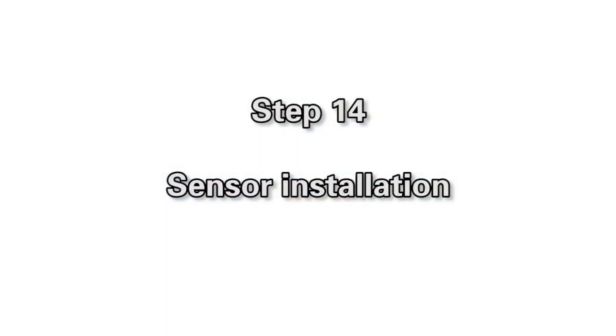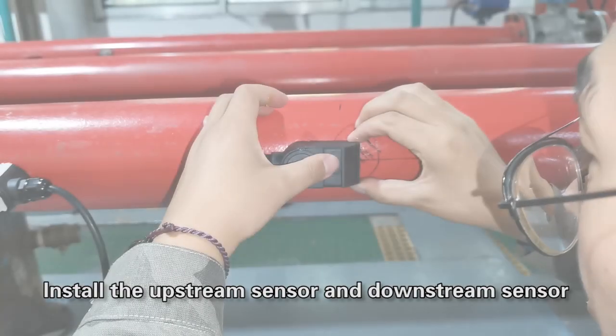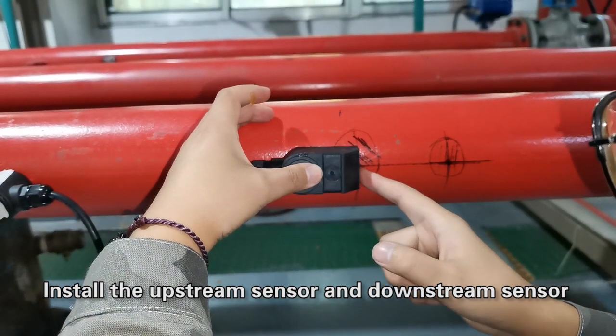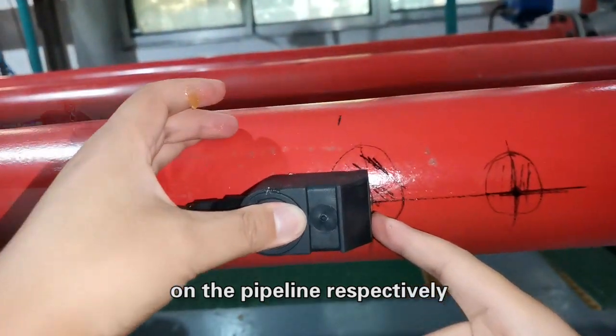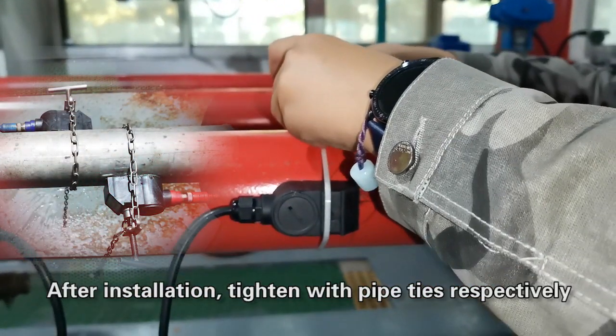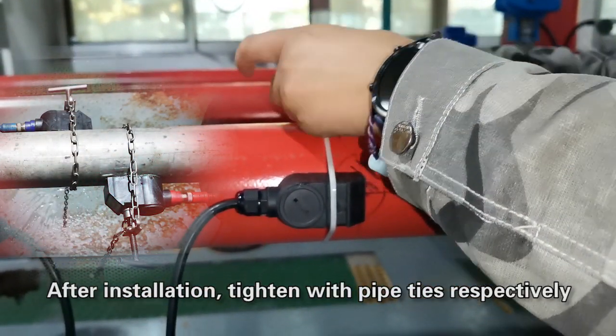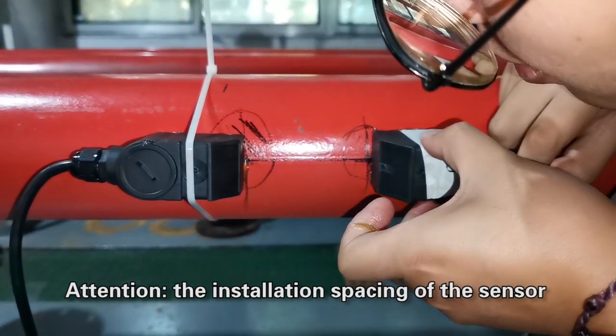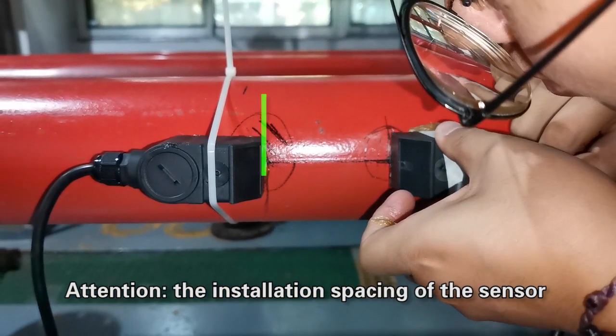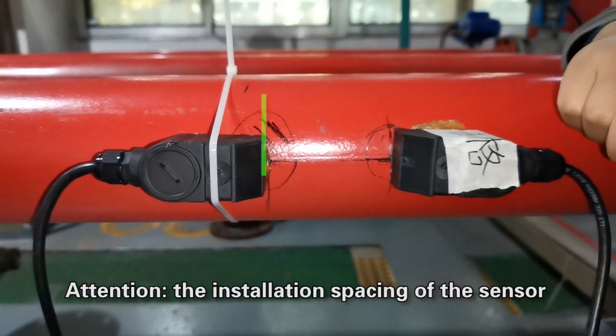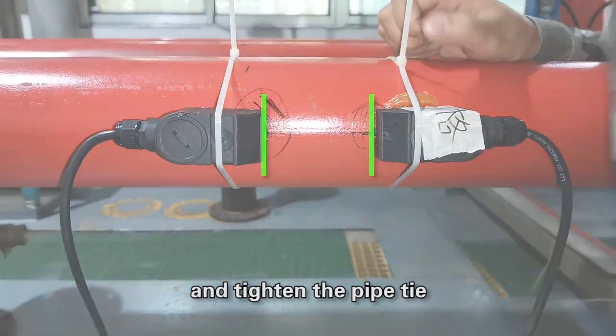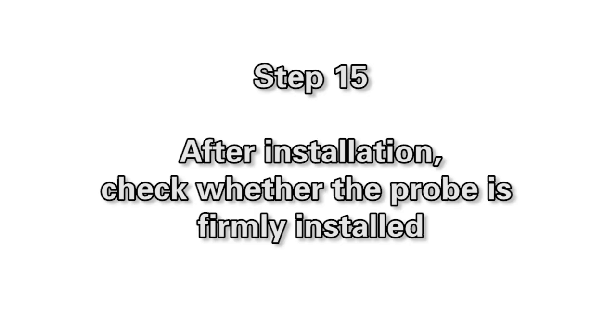Step 14. Sensor installation. Install the upstream sensor and downstream sensor on the pipeline respectively. After installation, tighten with pipe ties respectively. Attention, the installation spacing of the sensor is from top to top, and tighten the pipe tie. Step 15. After installation, check whether the probe is firmly installed.